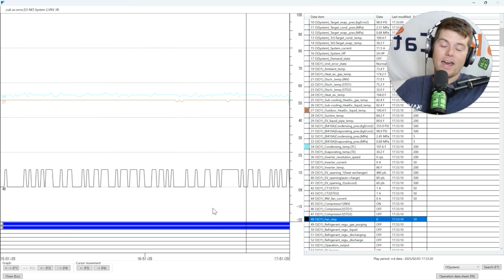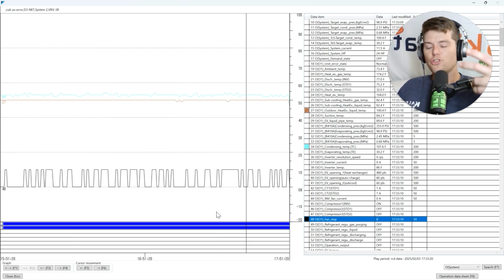And I can hang my hat on that every day. And people would think, well, oh my gosh, he's the VRV whisperer, right? He can hear them off in the distance crying for help. No, it's because I know from troubleshooting so many systems like this that when the fan does this and the system looks like that, it is undercharged 100% of the time. And it is very low on charge. And this system was actually 45 pounds light.